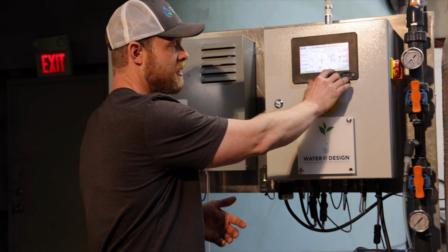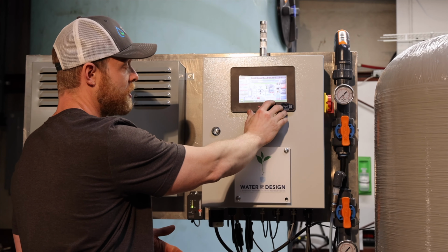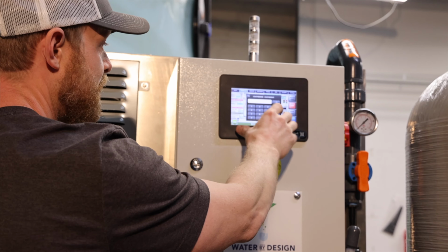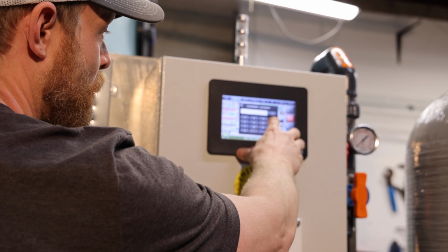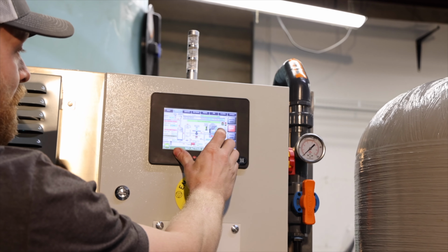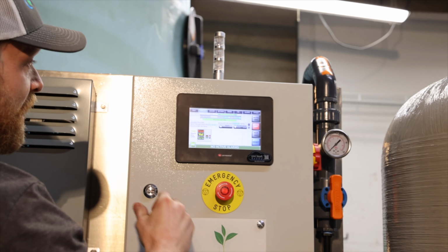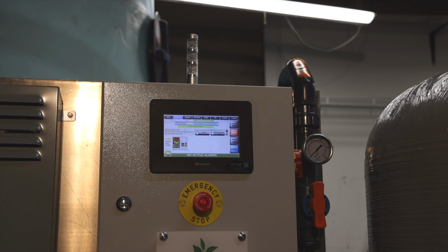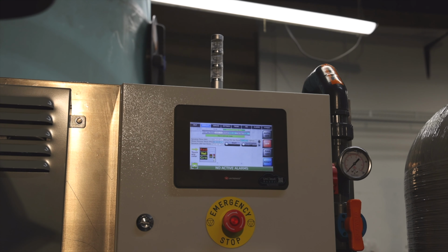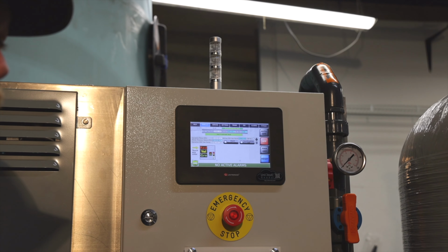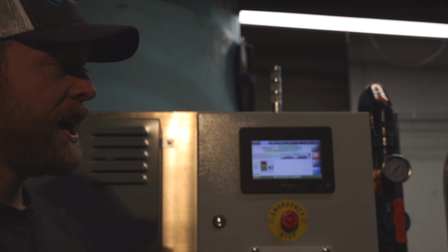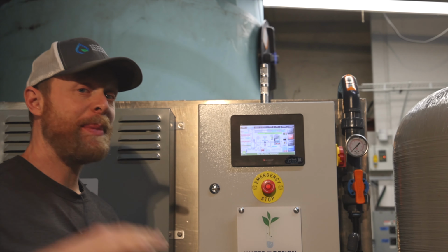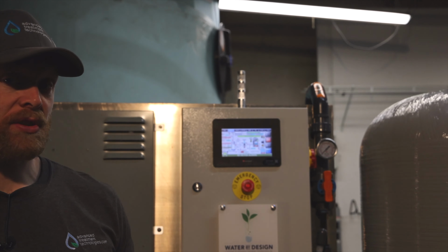CIP mode is indicated here, on page 1, the main page 1 control screen. You can touch right there. You can adjust your set point. This is different than the regular set point, which we've covered in another video. But you can also go to main page 2, and you can manually start and stop CIP mode there by pushing either sanitization on or off. Just by way of reminder, we've talked about this elsewhere, but during CIP mode, the ozone production gets ramped up. And we also open the actuated valve on the filter bypass manifold so that we bypass the filter and are able to keep more active ozone in solution.